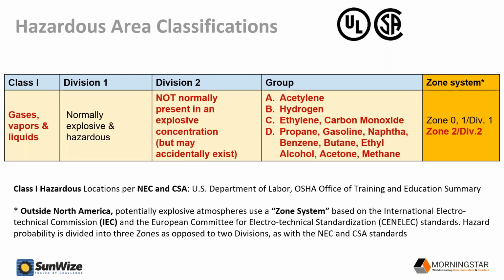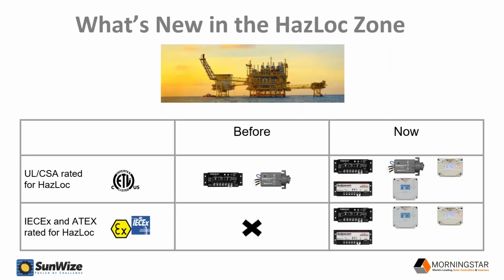So Division 2, or as I said, Class 1 Division 2, is what these products are actually listed for. And then the groups cover the different types of gases that may be present. On the right, you'll also see that across the listings that we have, there is a zone system as well, which is similar but differs somewhat from the Division 2 application. Zone 2 is also something that is normally not exposed to these types of concentrations of explosive gas, but could be. Those are the differences between the North American certifications and the international ones. Okay, next slide, please. So what's new?